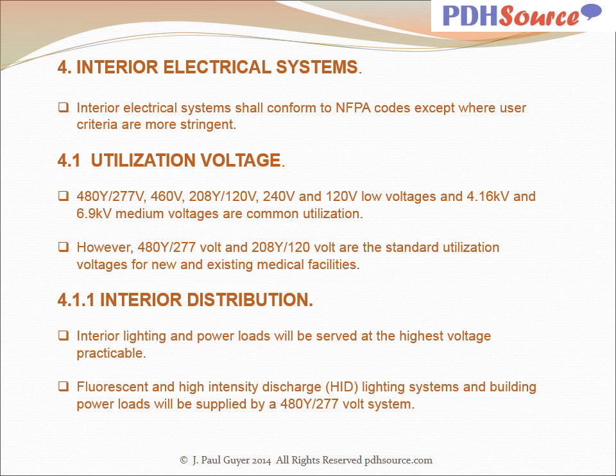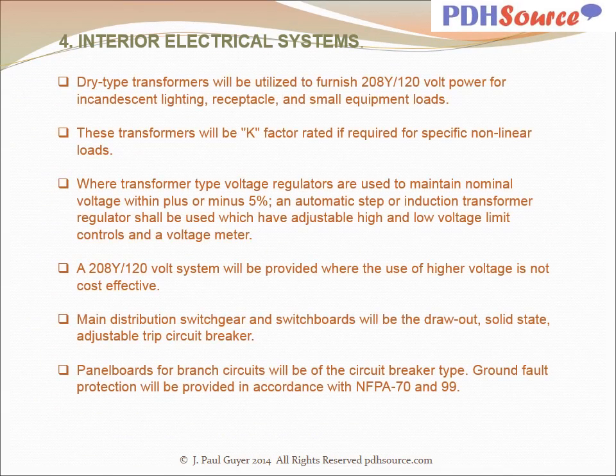Interior lighting and power loads will be served at the highest voltage practicable. Fluorescent and high intensity discharge (HID) lighting systems and building power loads will be supplied by a 480Y/277 volt system. Dry type transformers will be utilized to furnish 208Y/120 volt power for incandescent lighting, receptacle, and small equipment loads.